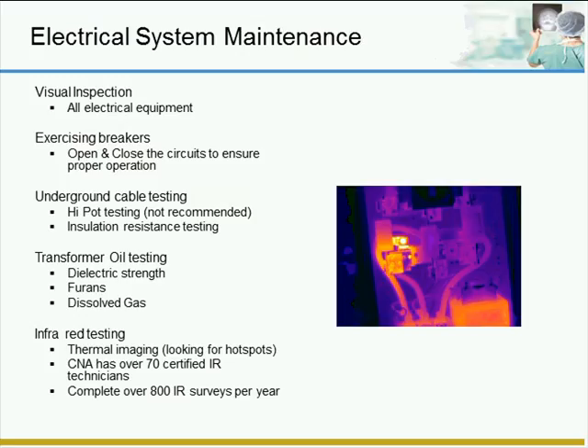The maintenance activities on an electrical system will typically include visual inspection, exercising all the breakers no less than annually, testing of the underground cable, typically at a hospital or medical facility, at a 3 to 5 year frequency. You'll want to do megger testing. There are other tests. I have a hipot test listed as well. That's a destructive test, not typically recommended. But megger testing is a non-destructive test, and you'll ensure that the underground cable is in good operating condition.